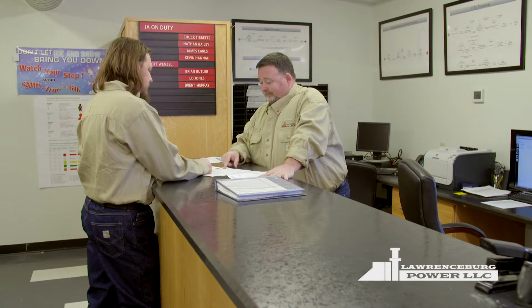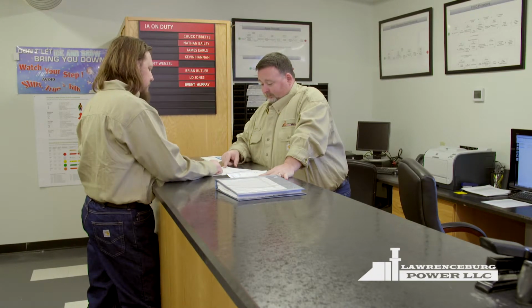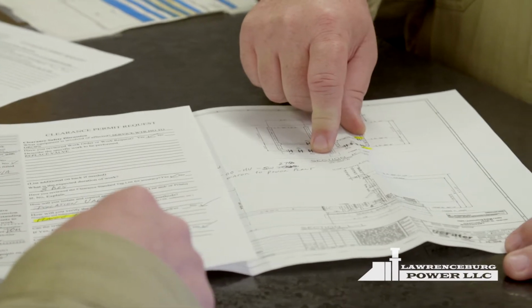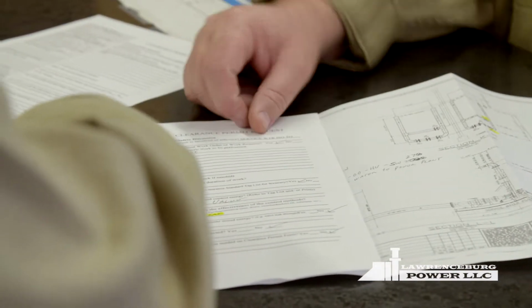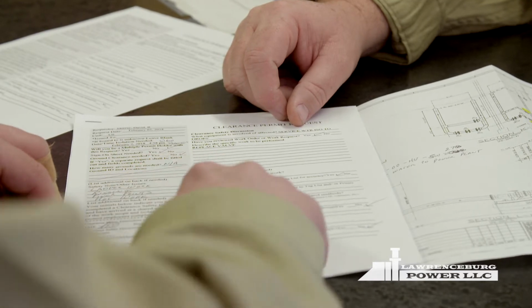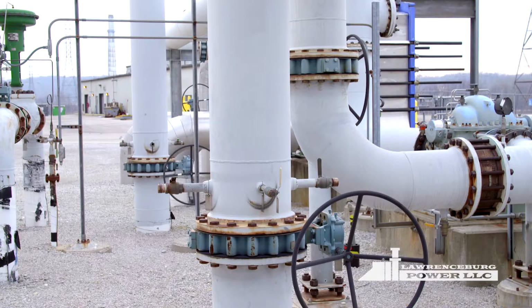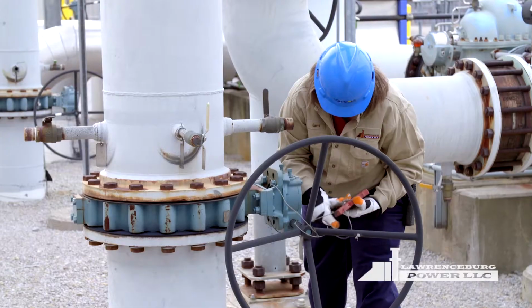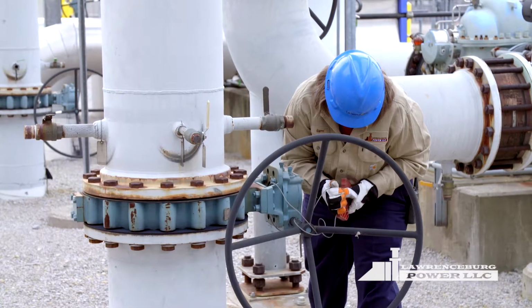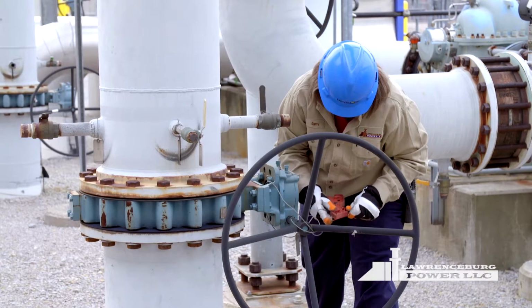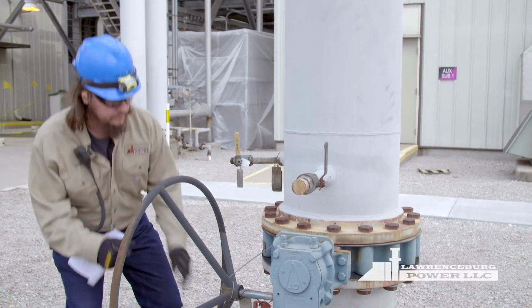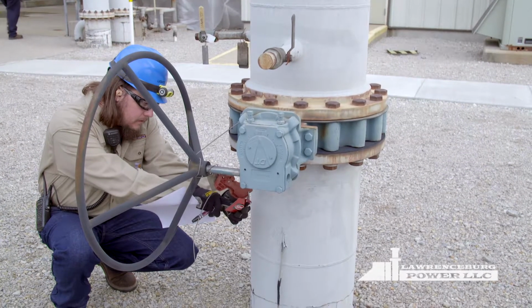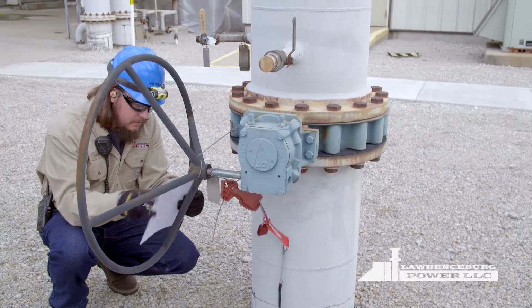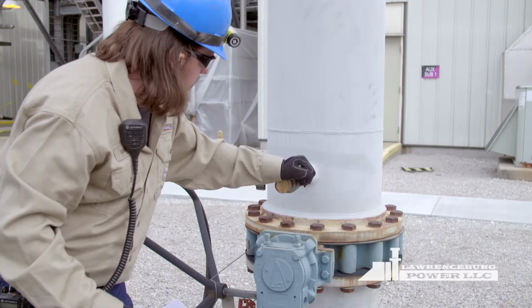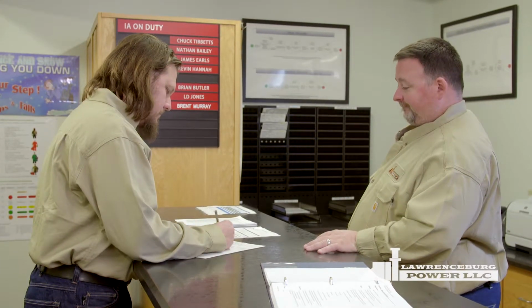Before work can begin, a Lawrenceburg plant employee must submit a permit request to the issuing authority. Both employees review isolation points, drawings, or any relevant material and discuss safe work practices. Once isolation points are agreed upon, a clearance is generated, and plant personnel will isolate the equipment, utilize red tags and locks, unless a lock will damage the device, and verify zero energy. After plant personnel have isolated the equipment, the permit holder will review all isolation points, verify zero energy, and initial the red tags. The permit holder will then accept the clearance permit, and the clearance is active.